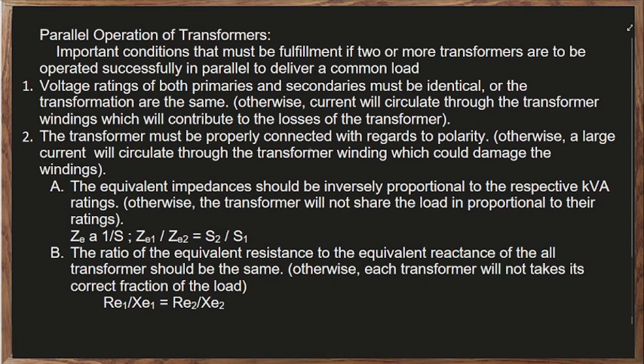The transformers must be properly connected with regard to polarity. So their polarity connections must be correct, no? If it is additive, additive; if subtractive, subtractive.